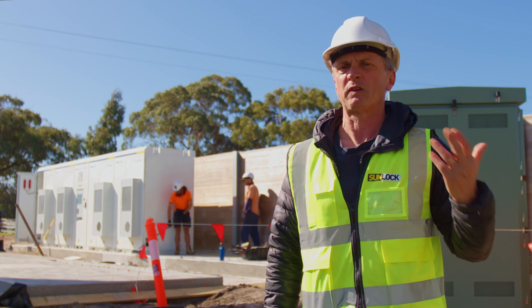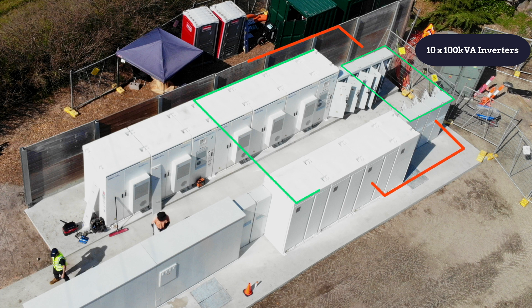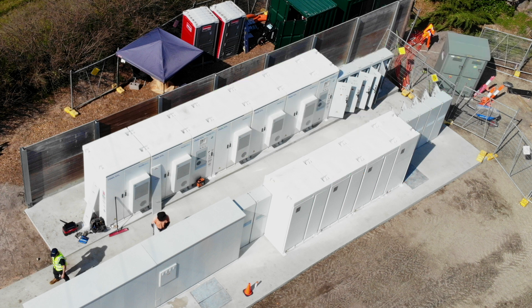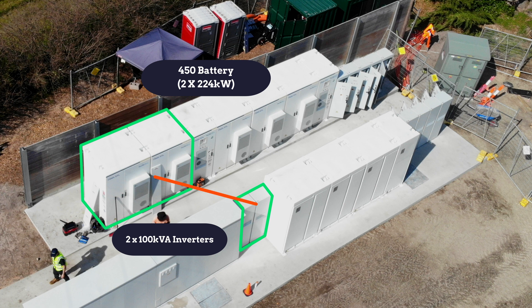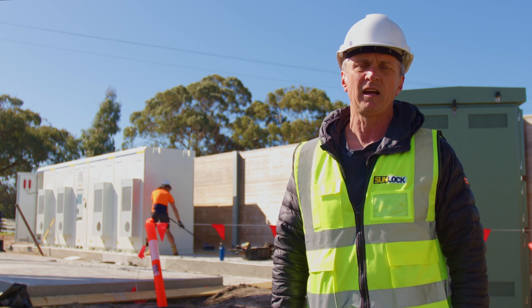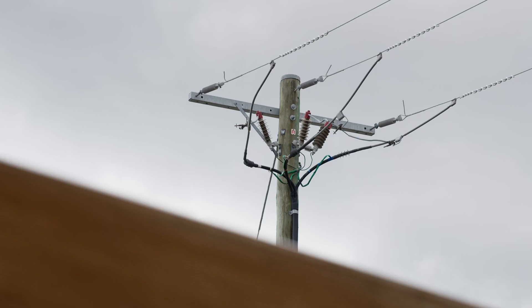Basically there are two separate systems because there are two NMIs. The first system is composed of 10 100 kVA inverters coupled to a two megawatt hour battery. The second system has 200 kVA of inverters coupled to an approximately 450 kilowatt hour battery bank on the second NMI. Both NMIs are fed by a 2000 kVA pad mount transformer, and there's a cubicle on site — it all falls under the United Energy distribution network service provider.